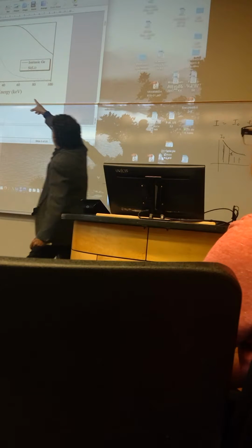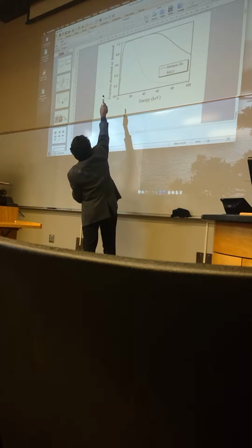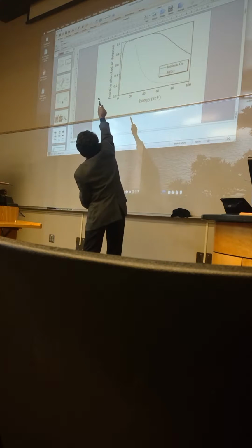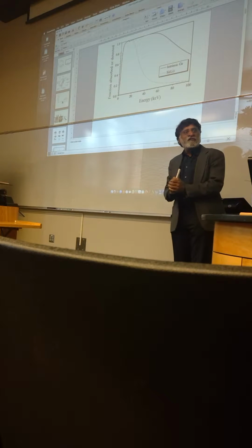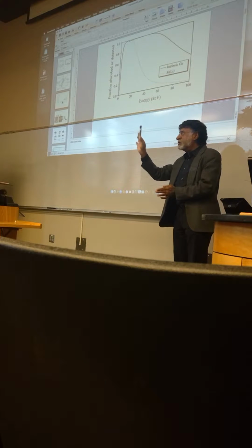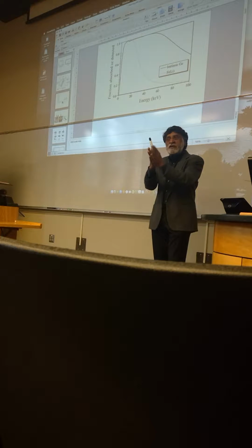So what I'm showing here in the next slide are essentially the efficiency curves. The dotted line is for the silicon drifted with lithium. You can see it's pretty good up to about 20 kilo electron volts. And then the efficiency drops. But if you go to the germanium detector, it stays quite highly efficient up to about 40 kilo electron volts. And then the efficiency drops. Is everybody clear on this point? That because of a finite thickness, the X-rays sometimes will just go through the detector without being detected.